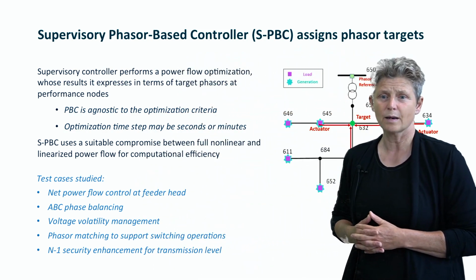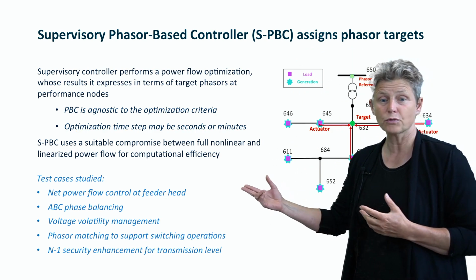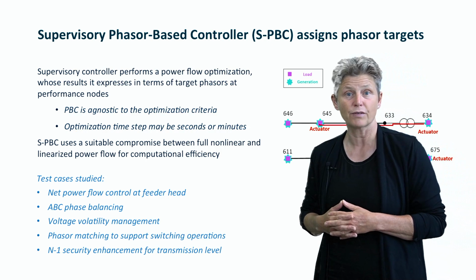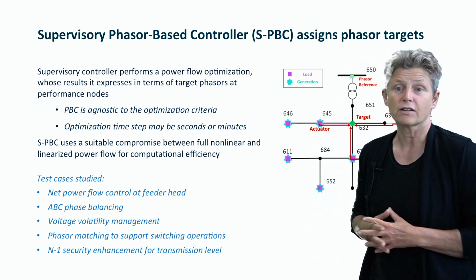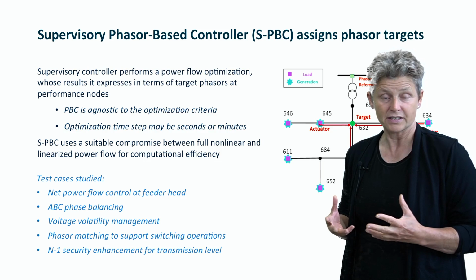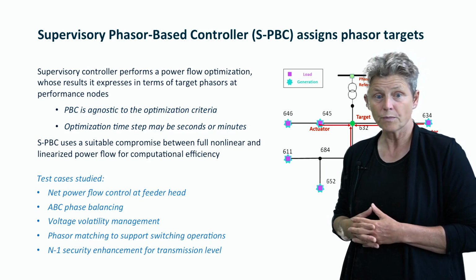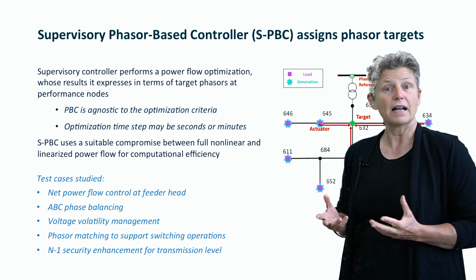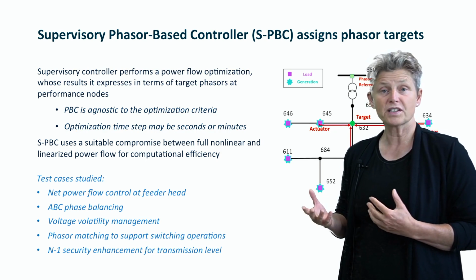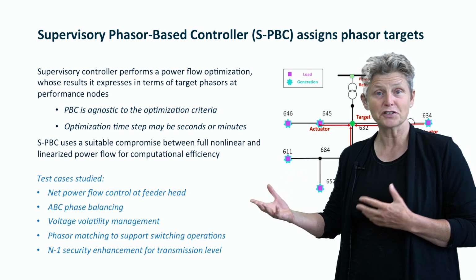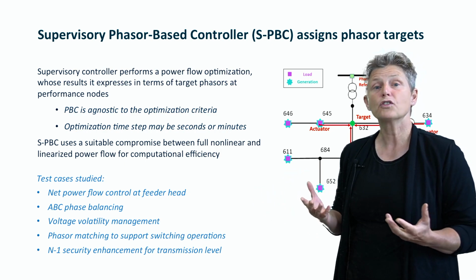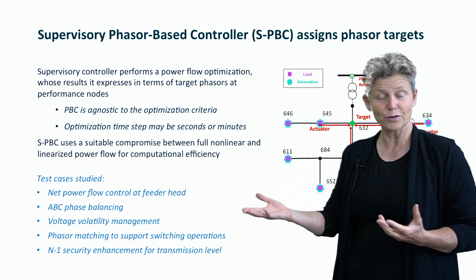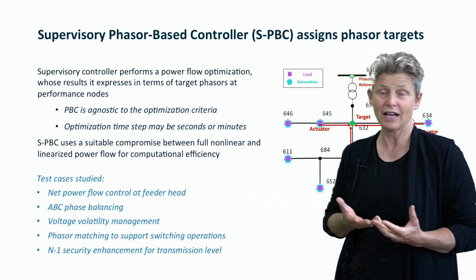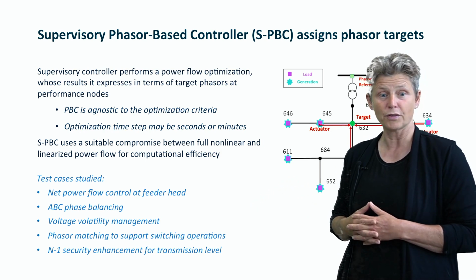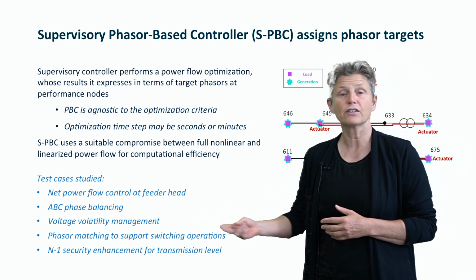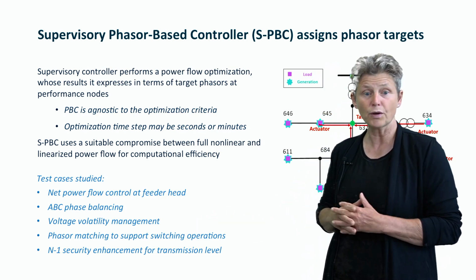That's just one example of a use case - to control net power flow, real and reactive, at the feeder head. We're agnostic here to what optimization criteria we want to choose. We may want to balance the three phases - if, for example, a lot of solar is connected on phase A and not so much B and C, we may want to tell the inverters at phase A to do something different than inverters or loads on phases B and C. We may just want to manage voltage volatility and keep the voltage magnitude within range.